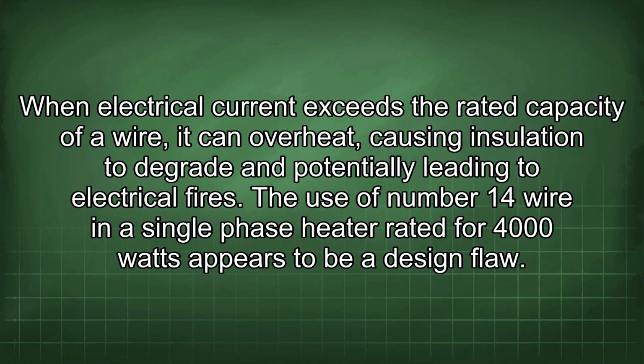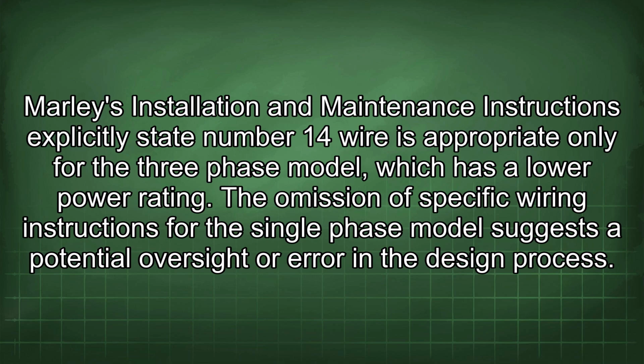When electrical current exceeds the rated capacity of a wire, it can overheat, causing insulation to degrade and potentially leading to electrical fires. The use of number 14 wire in a single-phase heater rated for 4000 watts appears to be a design flaw. Marley's installation and maintenance instructions explicitly state number 14 wire is appropriate only for the 3-phase model, which has a lower power rating. The omission of specific wiring instructions for the single-phase model suggests a potential oversight or error in the design process.